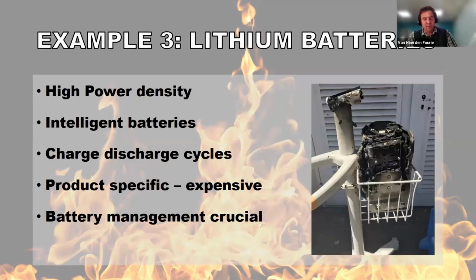Then the second example is the use of lithium-ion batteries in our facility. The lithium-ion batteries are quite popular in modern medical devices because of the high energy density. You get a lot of punch from a small package. Battery stability deteriorates with age, and battery management software is required to manage the batteries. The batteries are then spec'd to handle a specific number of charge and discharge cycles, and if you use them beyond that point, you have a risk of the battery overheating and igniting.